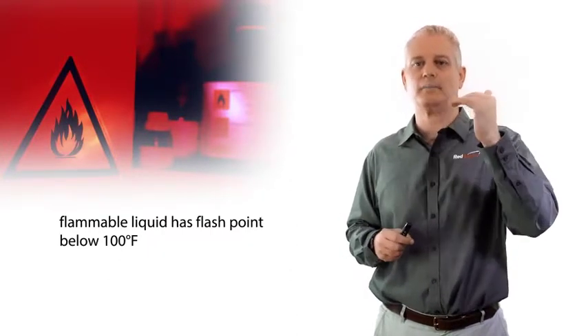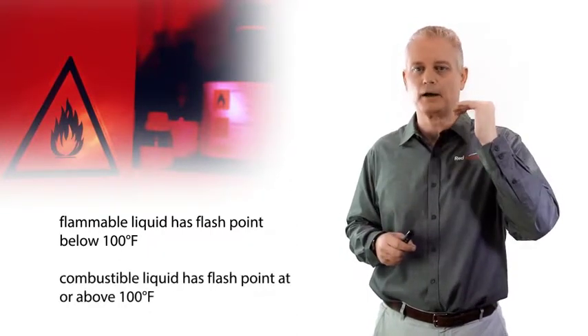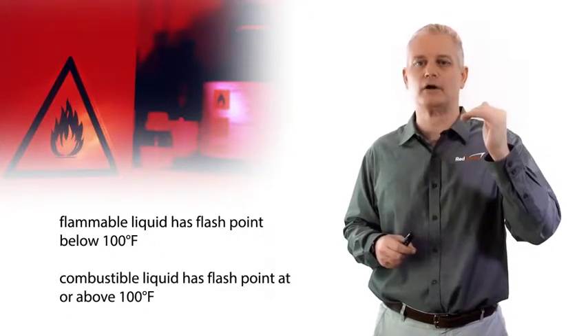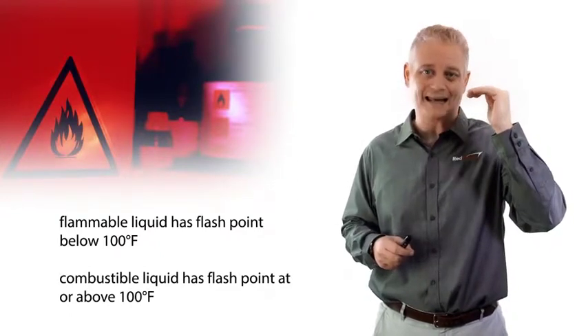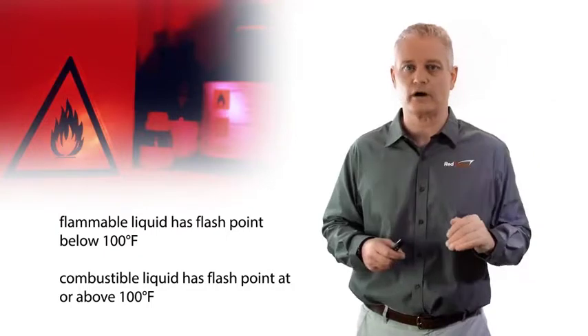If we're talking about a combustible liquid, a combustible liquid by NFPA 30 has a flashpoint at or above 100 degrees Fahrenheit. So diesel fuel would be an example of a combustible liquid. It will still ignite but at a much higher temperature.